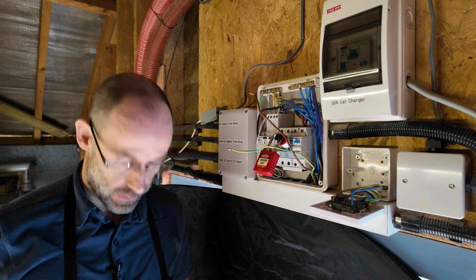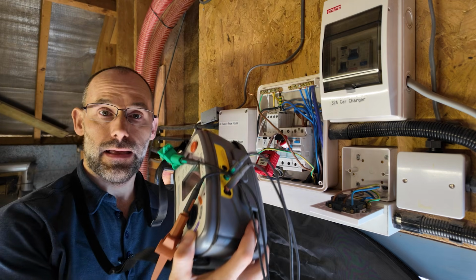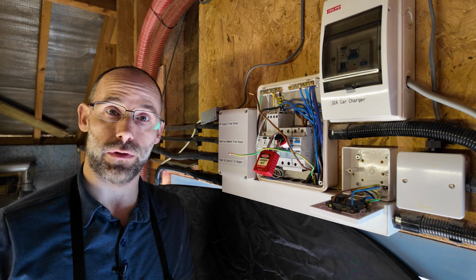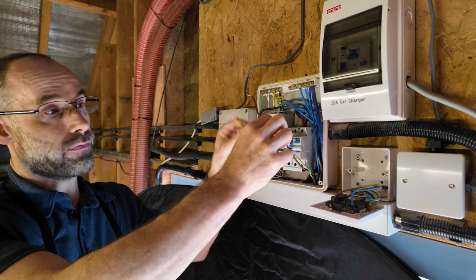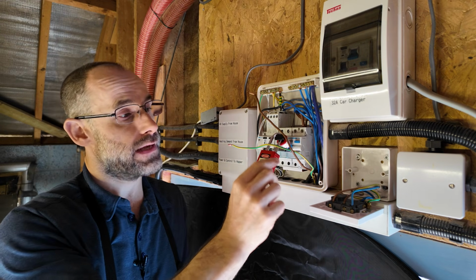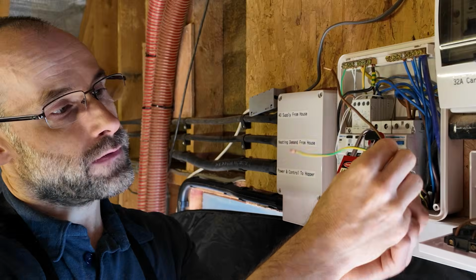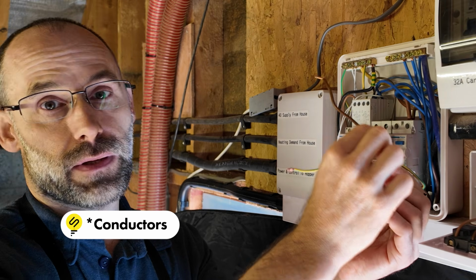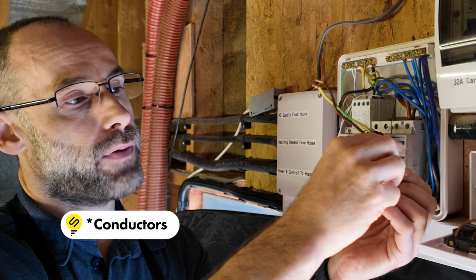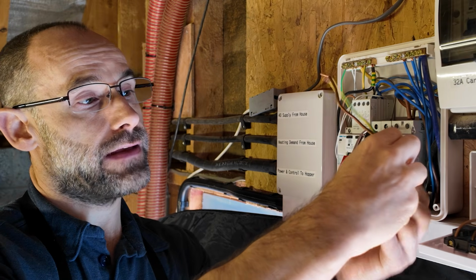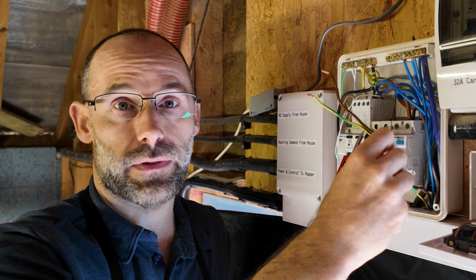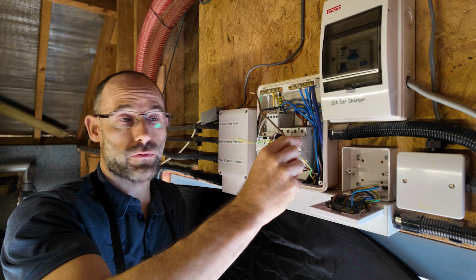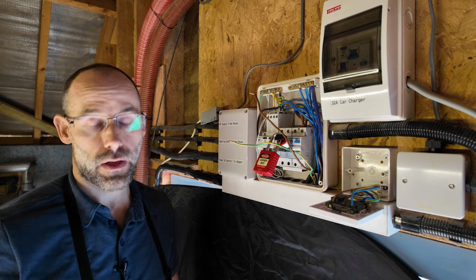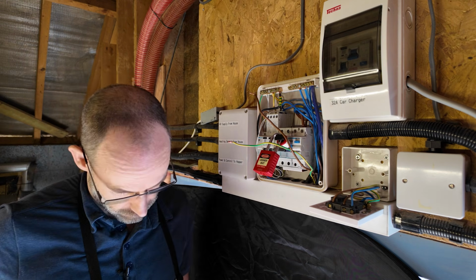Now, one of the reasons these chunky meters are so chunky is because they can generate test voltages and put them down these wires. So what we're going to check next is insulation resistance. It's going to make sure that these sheaths between these wires here, these PVC sheaths, are actually perfectly intact all the way down, and there is no contact between the wires, because that would be a short circuit. That could cause arcing, that could cause all sorts of problems. So this next test is something called an insulation resistance test.